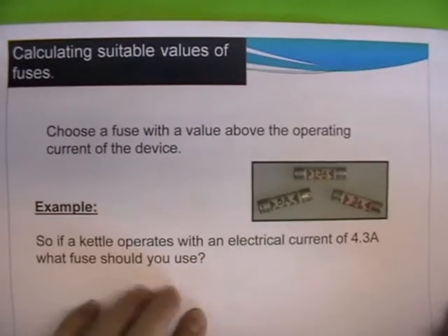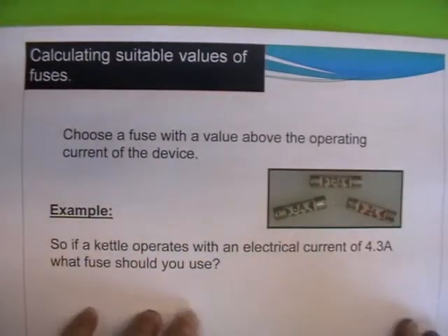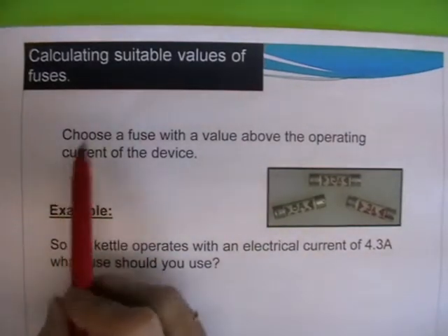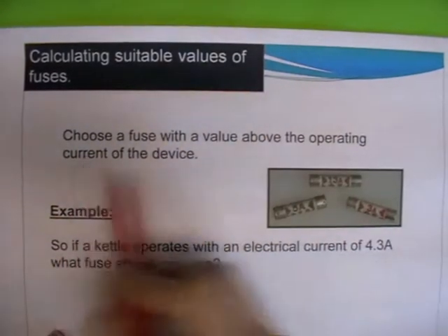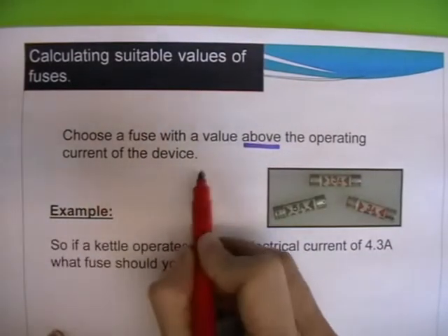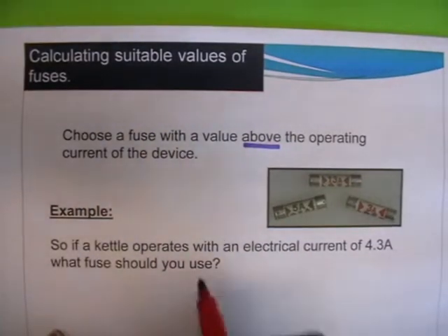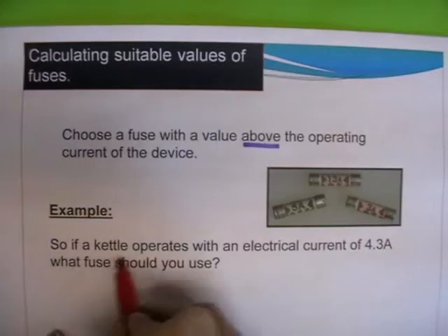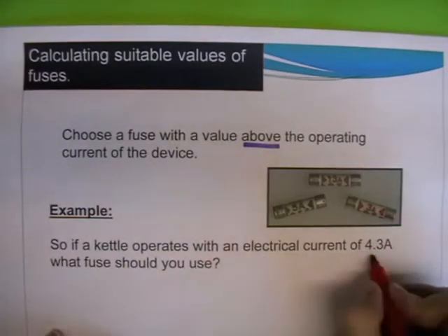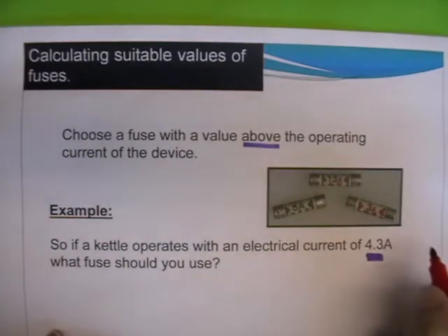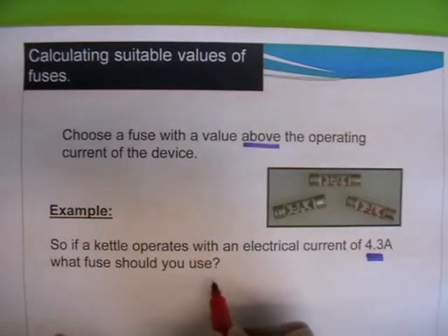This is how you calculate the suitable value of a fuse. First, choose a fuse with a value above the operating current of the device, so there's enough current to allow your device to work. In this case, if a kettle operates with an electrical current of 4.3 amps, it needs 4.3 amps to work, so the fuse you choose should be above that.